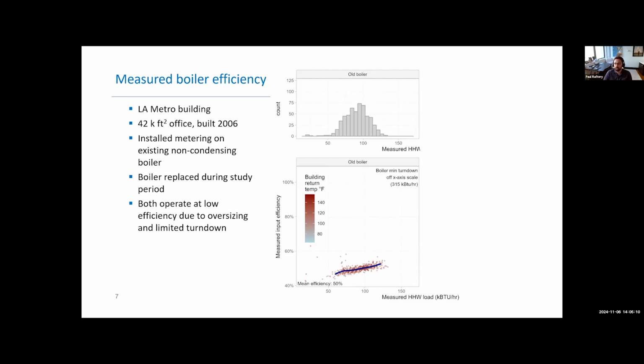And the average efficiency of this unit over the course of the year was 50%. And the nominal efficiency of this unit is 80%. So an enormous opportunity there. And one of the primary reasons is it's oversized, it's old equipment, and it doesn't turn down well. But an interesting thing happened in this particular site. That boiler actually failed during the middle of the study. And we only found out about it about a month later when we went back to download some more data. And at that point, the building owner had already replaced the boiler without reaching out to us or anything. So they didn't take into account any of the data that we were collecting for sizing it. And they put in a new unit.